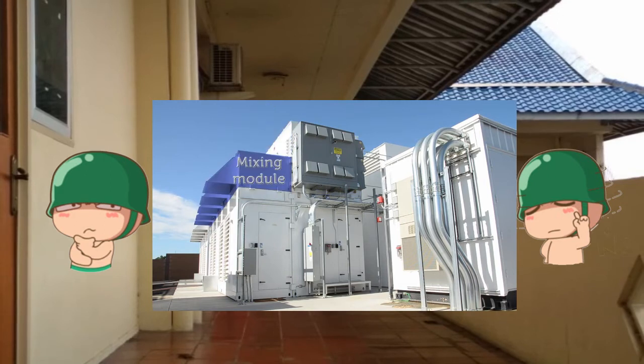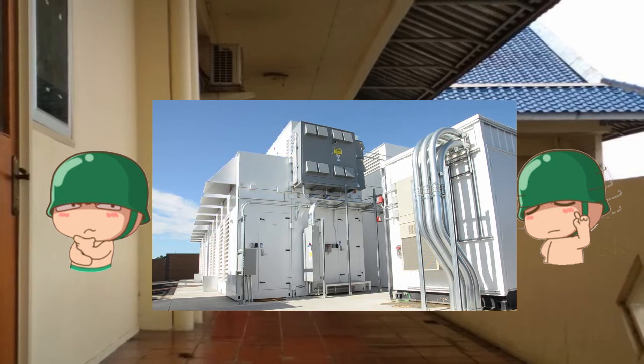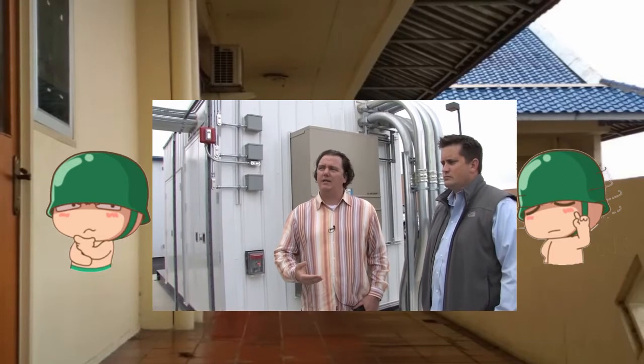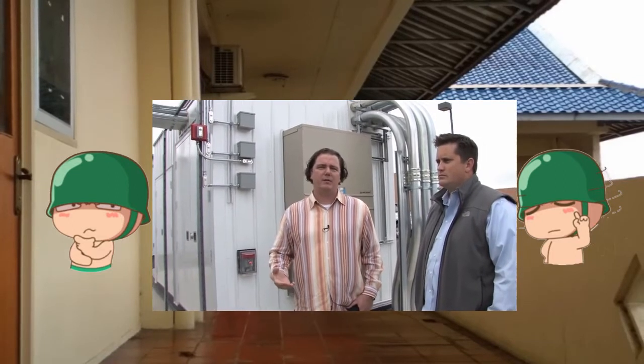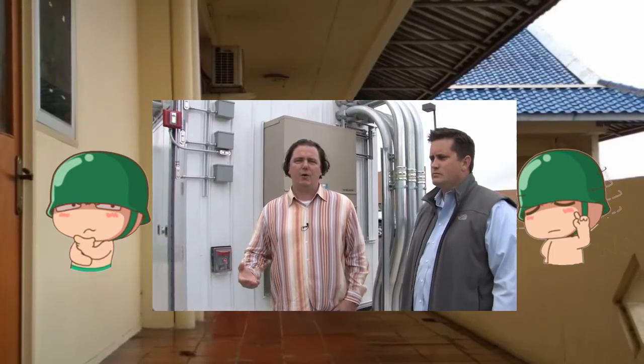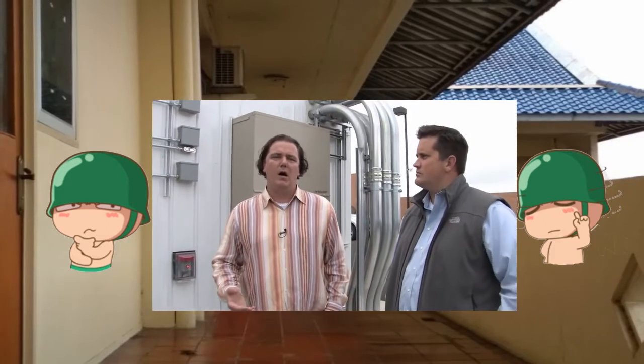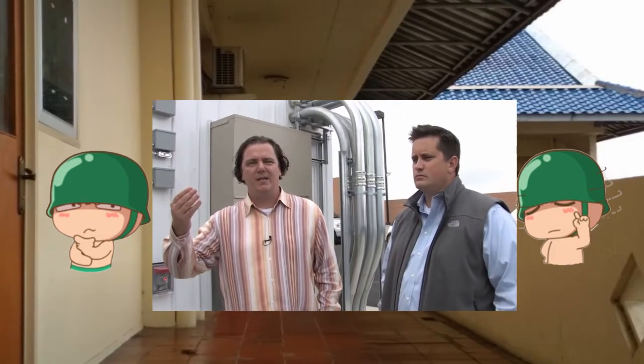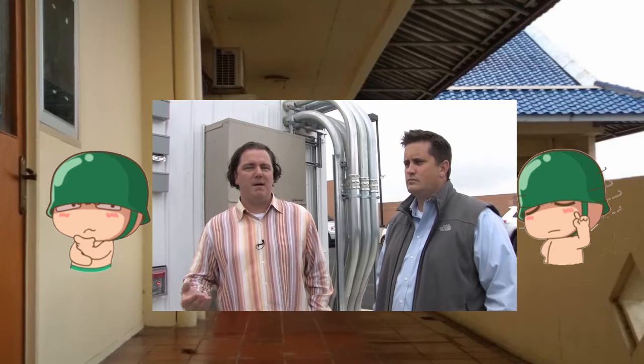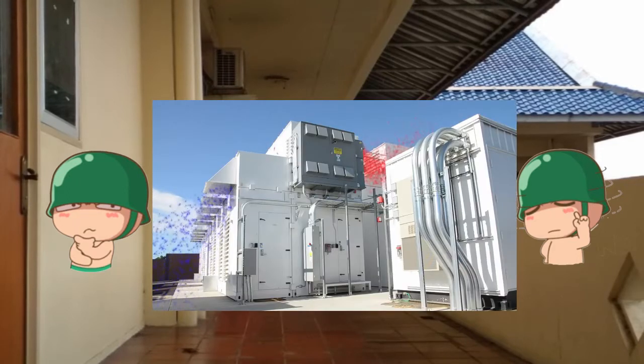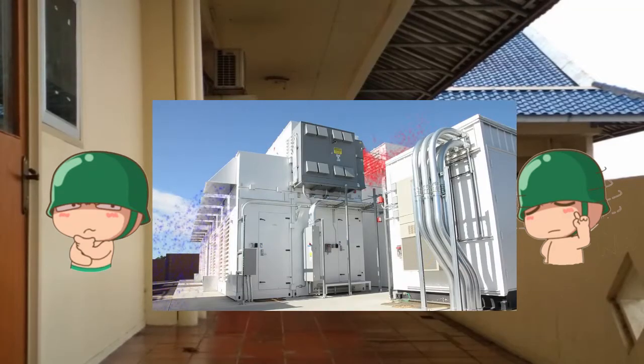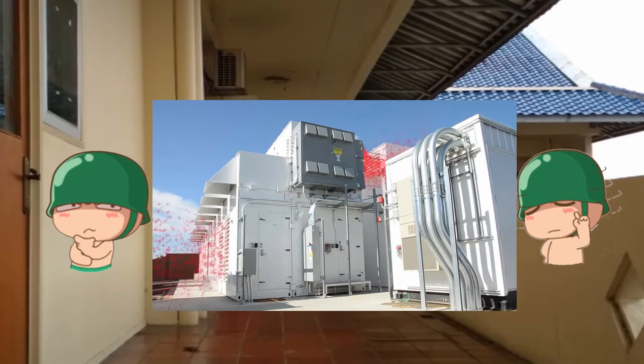The topology of these modules: you have an IT module, an evap cooling module, an air handler module, and a mixing module. Depending on how hot or cold it is dictates what mode of operation this module is in. For instance, today we are going between a day cold enough to warrant a mixed mode to a warm enough situation where evaporative cooling is turned on and we're cooling in an evaporative mode.